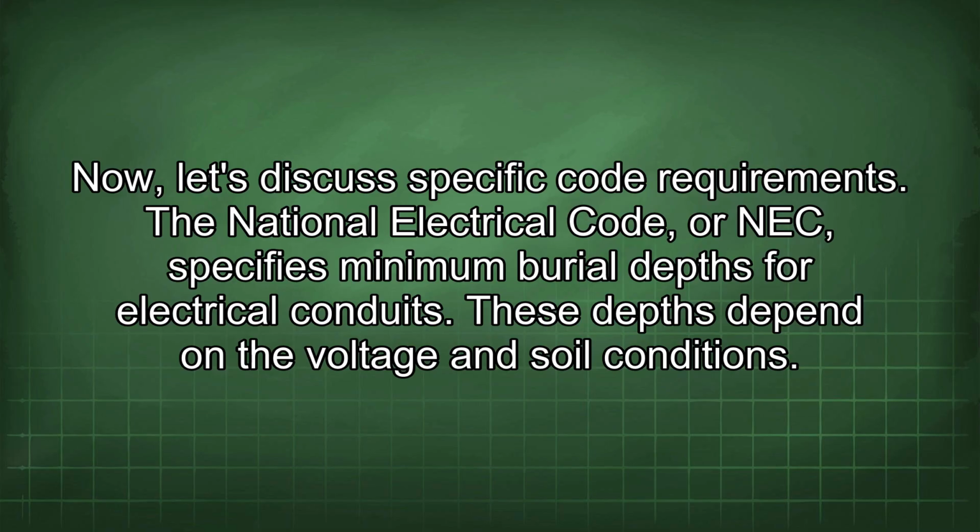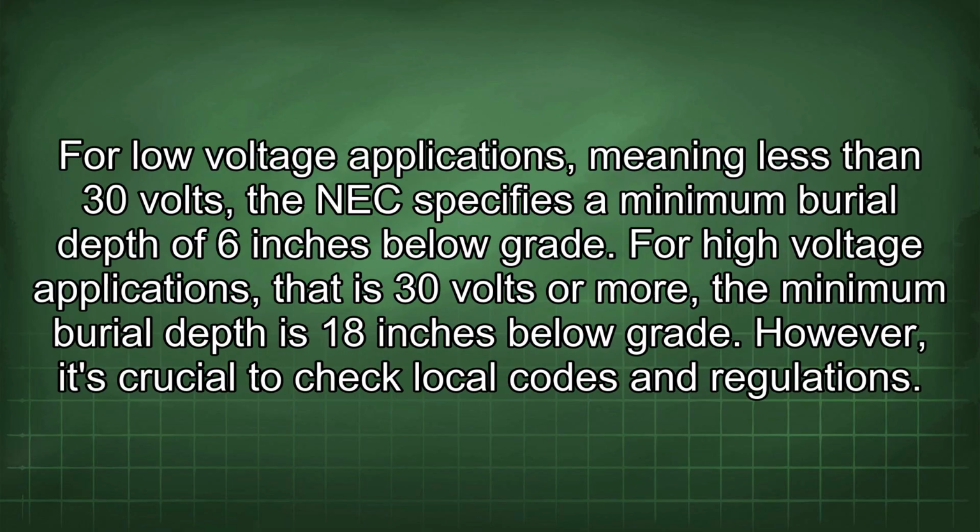The National Electrical Code, or NEC, specifies minimum burial depths for electrical conduits. These depths depend on the voltage and soil conditions. For low voltage applications, meaning less than 30 volts, the NEC specifies a minimum burial depth of 6 inches below grade. For high voltage applications, that is 30 volts or more, the minimum burial depth is 18 inches below grade.